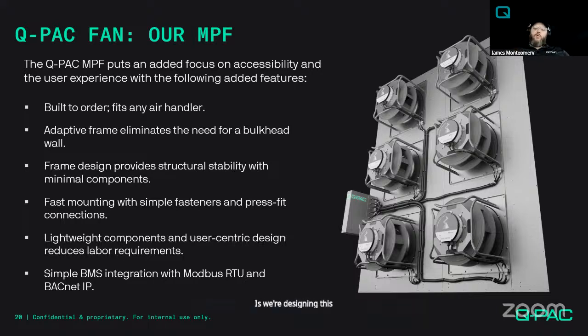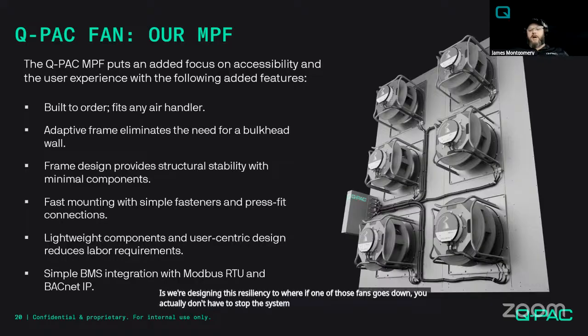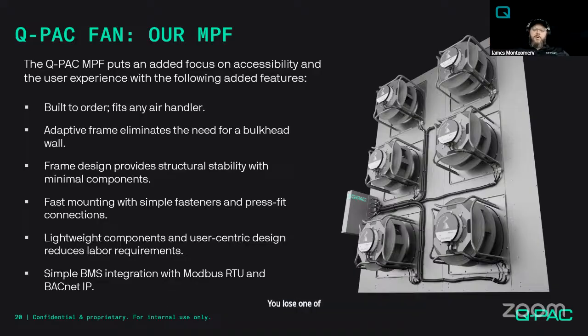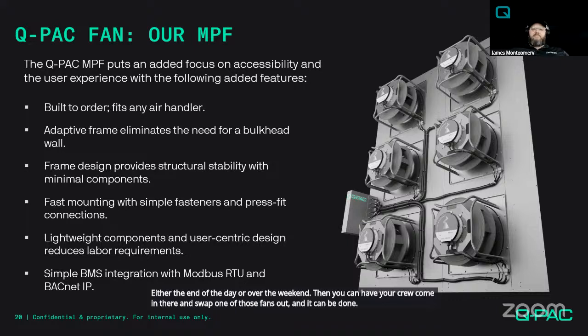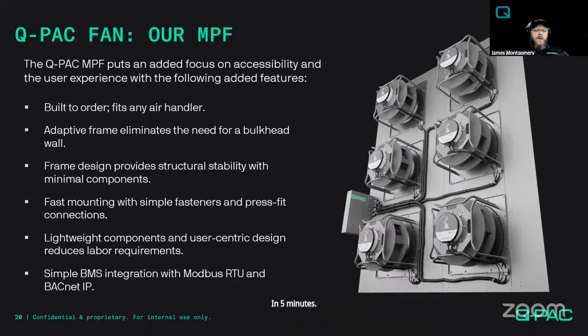And so in our plan and in the MPF, what we're doing is we're designing this resiliency to where if one of those fans goes down, you actually don't have to stop the system. You have no loss of air. You're not even limping in an N-1 configuration. You lose one of those individual motors, the rest of the motors ramp up based on demand, and you still meet your requirement. Now, when occupancy is low, either the end of the day or over the weekend, then you can have your crew come in there and swap one of those fans out, and it can be done in 5 minutes. So that's the lightweight components.